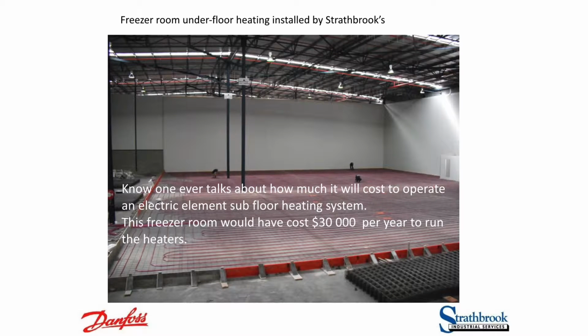Interesting, this floor, had they gone ahead with the electric defrost that was originally proposed by other contractors, would have cost $30,000 a year to run the heaters in the floor alone. No one ever says how much is it going to cost to run the floor. They're always thinking about the compressors and the fans. The floor can cost as much as all of your fans put together times 2. Incidentally, that floor costs about $400 a year to run a little pump.